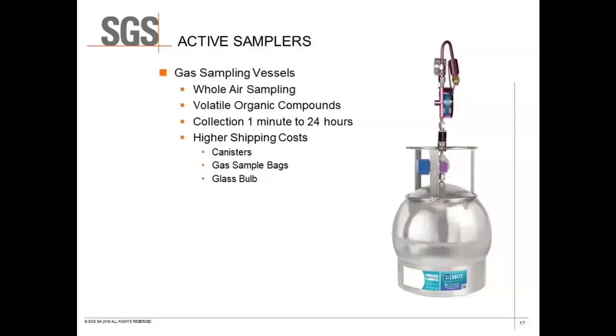Gas sample bags offer another option for whole-air collection. There are a variety of bags available for collecting gas samples — a little more convenient in terms of bulk — but they have drawbacks including shorter holding times and difficulty shipping by air due to pressure differentials in flight. You cannot collect a completely full sample into the bag; you have to leave room so that when it goes up in an airplane at a different pressure, the sample bag can expand without bursting. There are also glass bulbs available for collecting into a glass container.